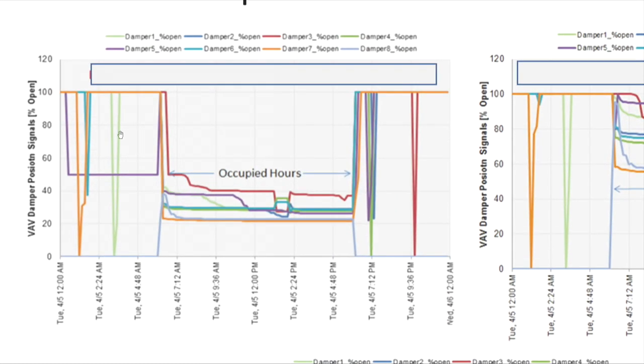I'll take a stab at the first one, if I may, Michael. Judging by how low our damper percentages are during occupied time, we're running too much static pressure from that air handler. Those dampers should be trending much closer to the top, otherwise we're wasting a lot of energy.